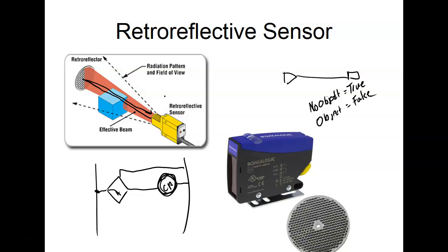The problem here is that we can't use this to detect items that are transparent, right? So that would be one disadvantage. The other disadvantage is that if you're in a dirty environment, not even an extremely dirty environment, you're going to have to clean it. The guys in Brooklyn said that's one of the things we have to do. I forgot how often it is. Go out and do a lot. I mean, all these optical sensors, right? Even though a company is as clean as Brooklyn is, there's still a lot of oil and stuff.